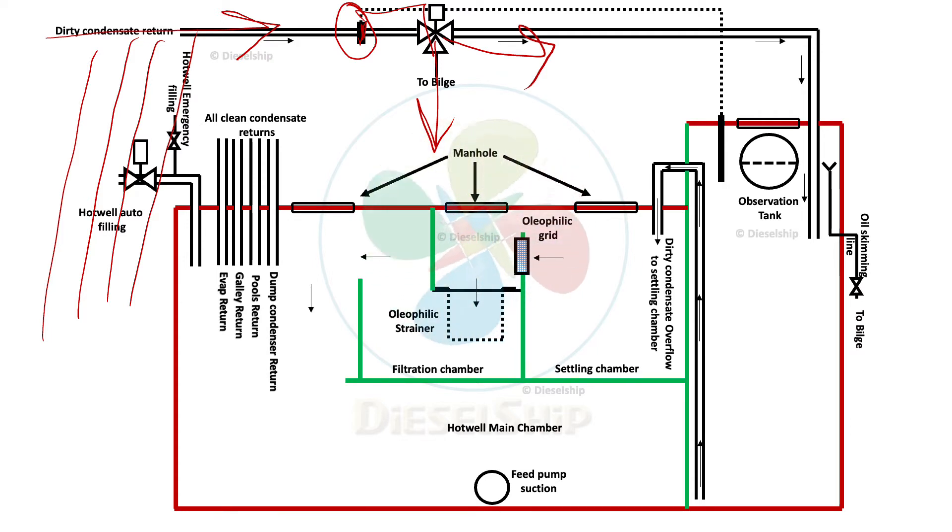There is also another oil sensor here in the observation tank itself. If there is any oil detected there, that will also trigger the three-way valve to open. In most systems, even the dump condenser has a three-way valve because it is cooled by seawater. There may be seawater contamination, but there it is a salinity meter that controls the three-way valve, either putting it to the hot well or dumping it to the bilge.